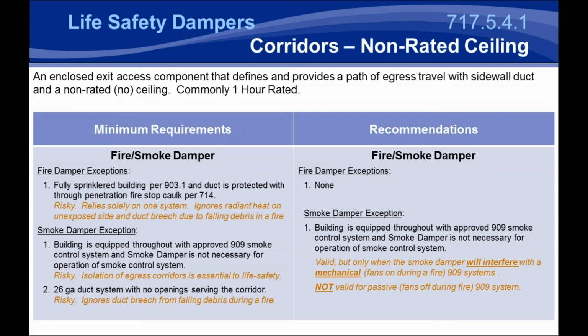We think the fire smoke dampers are recommended because corridors are essential for people to get out of the building. They're designed to allow a path of egress. They're commonly 1 hour rated, and they're allowing people to get out of a building in an emergency. Because of that, we want to restrict the amount of fire and smoke that gets in as much as possible to allow people to get out with the most amount of time before the building starts to degrade in this emergency. Now, there are some exceptions, fire damper and smoke damper exceptions.